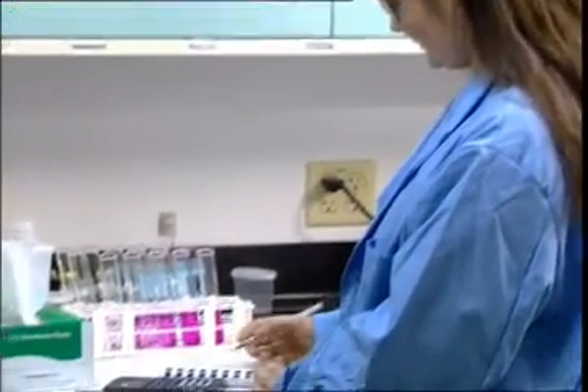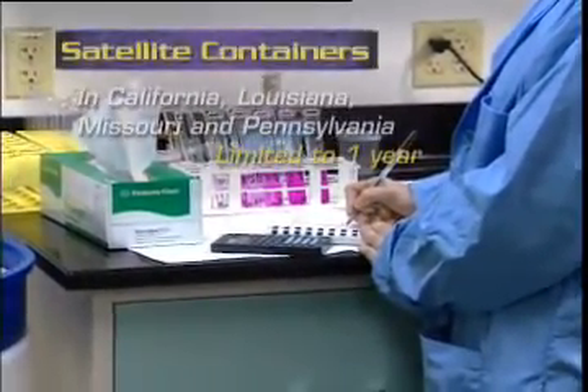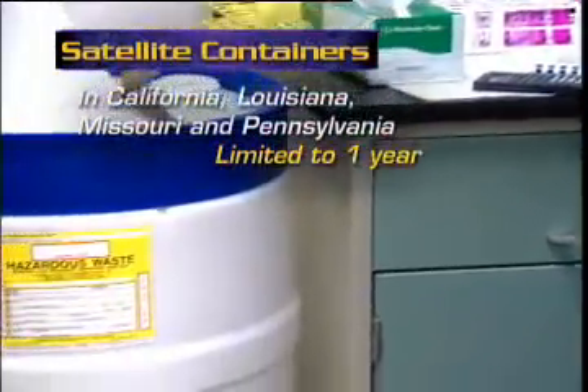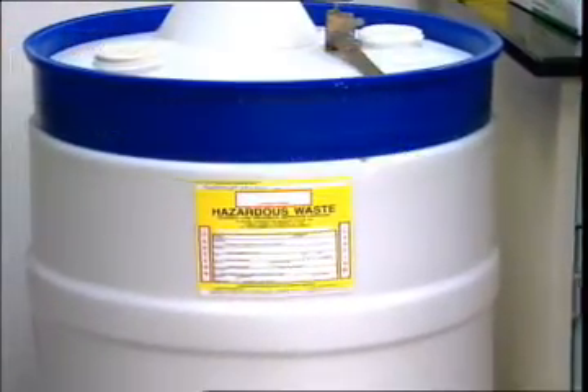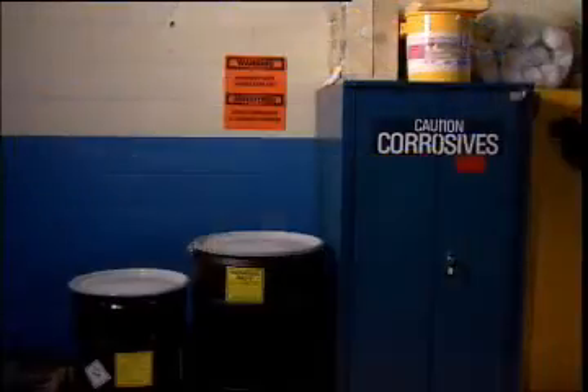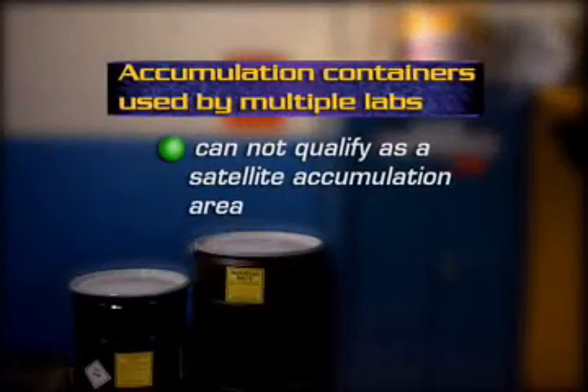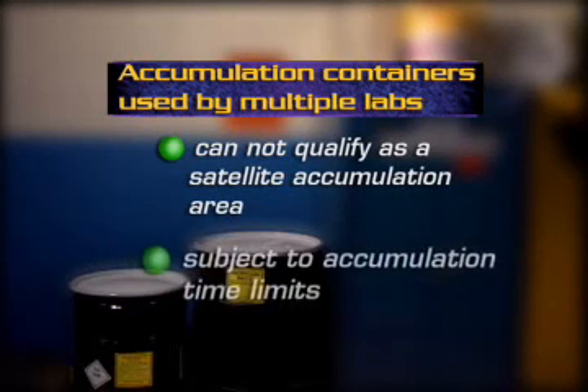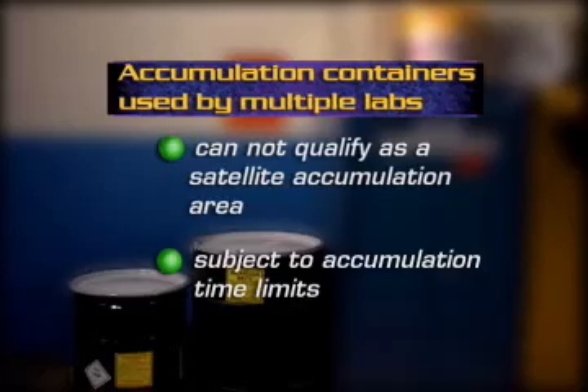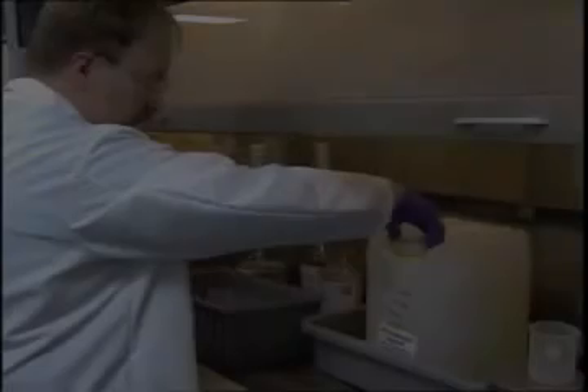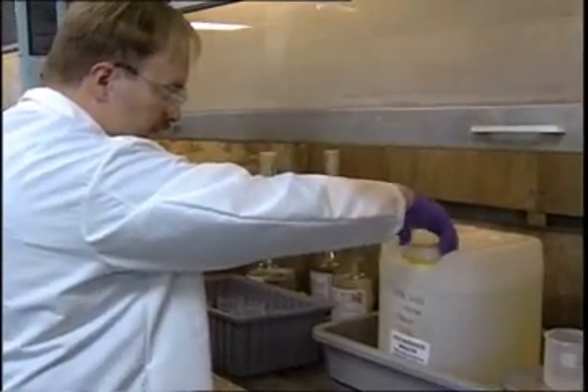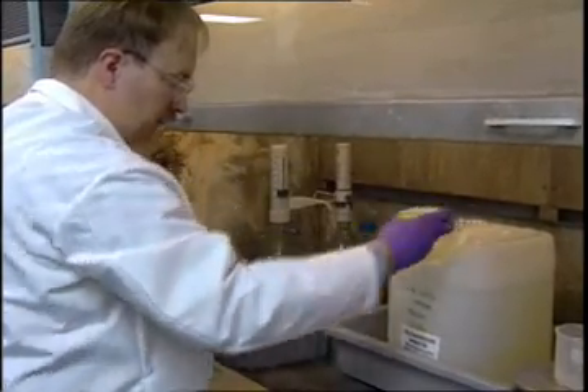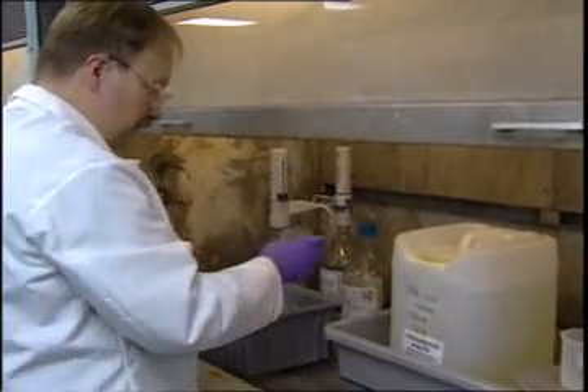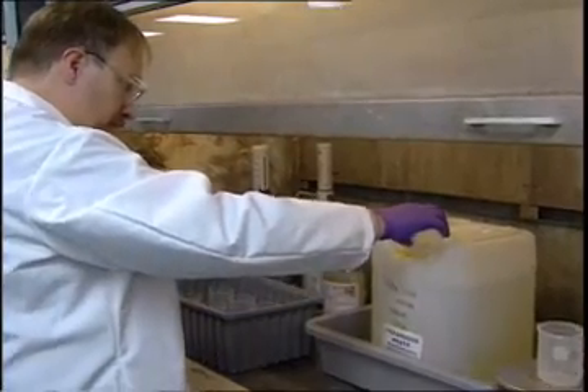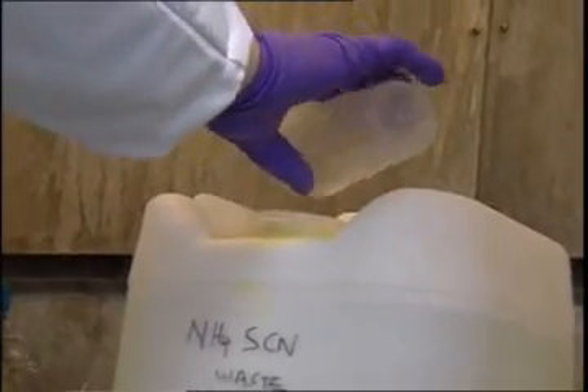A lab may accumulate wastes in a satellite container without any limits on how long the wastes may remain in the lab. However, a container used to collect wastes from several physically separate labs or other generating facilities cannot qualify as a satellite container and therefore is subject to accumulation time limits. Satellite accumulation must be strictly managed according to regulatory standards. Satellite areas must be under the control and oversight of the trained scientist or technician who generates the wastes accumulated there.